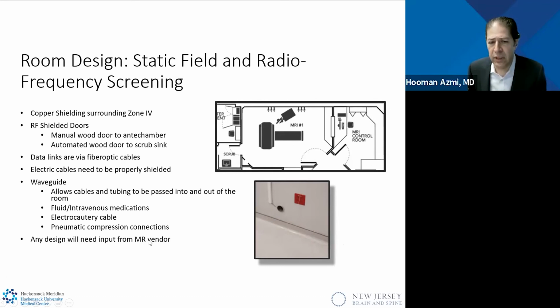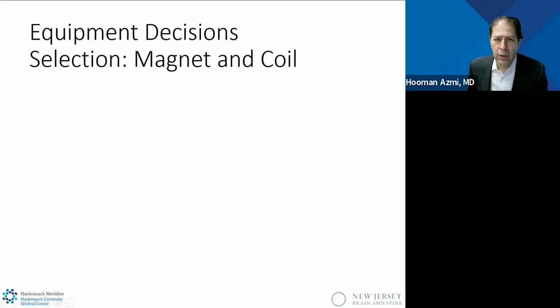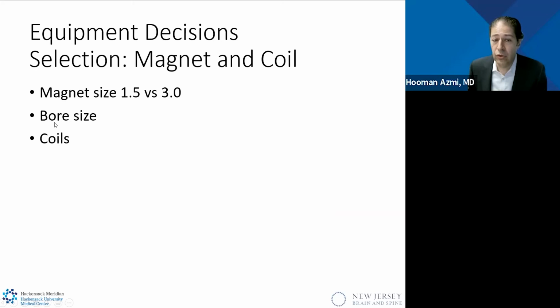And of course, any design will need input from the MRI vendor. So magnet and coil selection, obviously there are options for 1.5 Tesla, 3 Tesla. So much goes into that. We chose a 1.5 Tesla with a bore size of 70 centimeters, and even nowadays all of these magnets have a fairly large bore size. Coils, we chose flex coils. I'll show you a picture because we had to for ClearPoint. But that goes into our decision making.